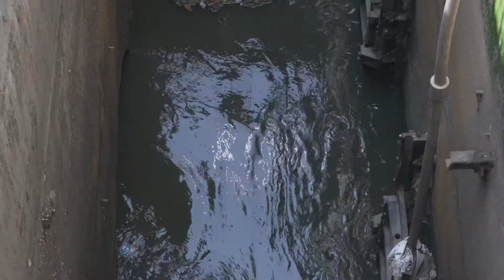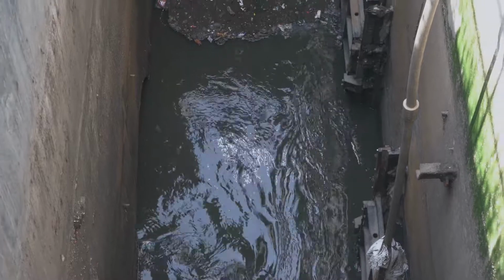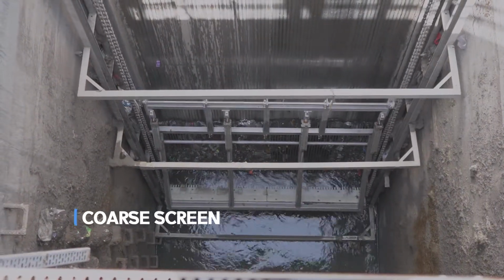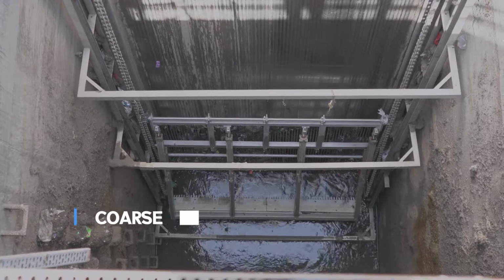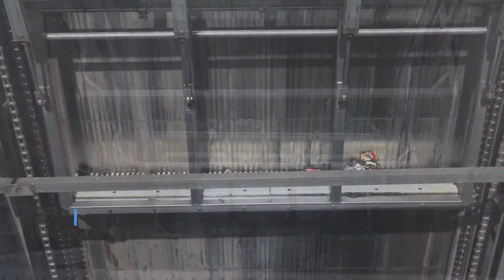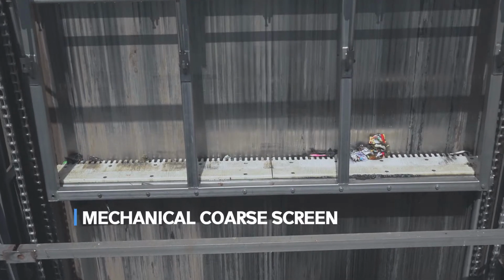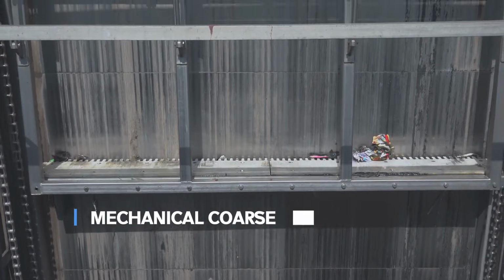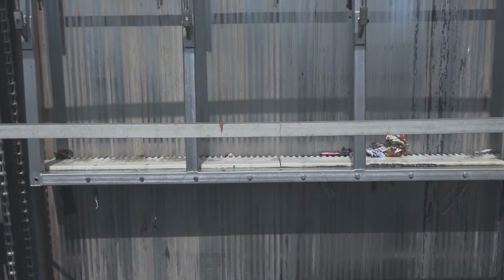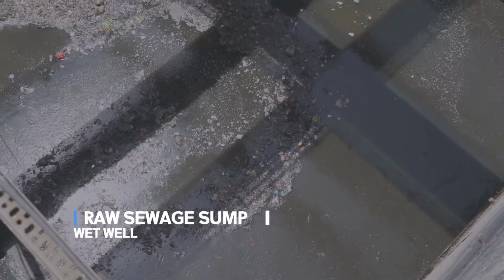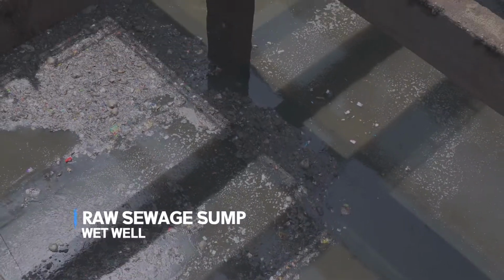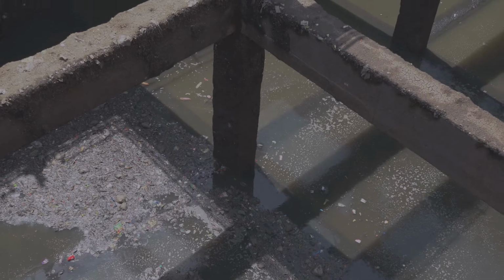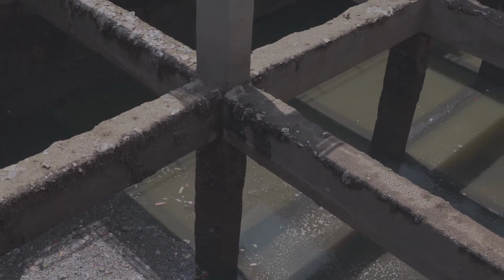A pipe is provided to receive the flow of 120 MLD to the inlet chamber. Raw sewage from the inlet chamber enters into the coarse screen for removal of floating debris. 4 parallel channels are provided, with 2 each being allotted to mechanical and manual coarse screen. After coarse screening, raw sewage enters the sewage sump, which is designed on the basis of peak flow with a hydraulic detention time of 5 minutes.